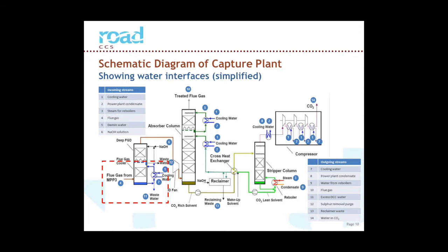And this stream, excess DCC water, the wastewater, is really quite significant. In fact, the DCC cools the flue gas to the point where there's actually less water in it than there was when it went into the FGD. Then we have the deep FGD, and that's a much more minor component. So it's basically a simple closed loop. There's sodium hydroxide added and sodium sulfite and sulfate coming out in the waste stream, but they are very small streams. They're less than 1 ton an hour. Well, all the small streams combined are less than 1 ton an hour.